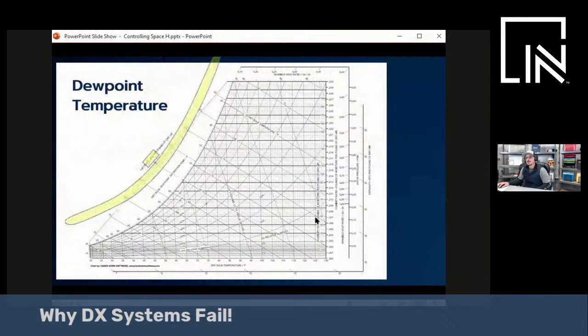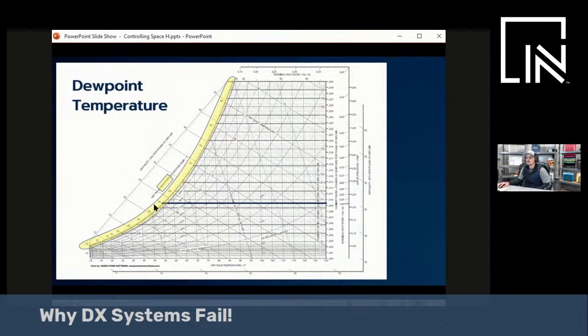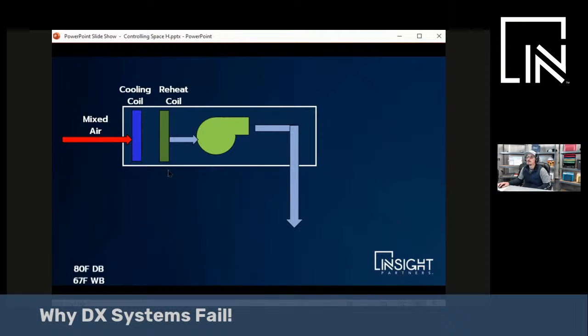If we go to our psychrometric chart, and I also have a couple videos on psychrometrics, welcome to check those out. We draw a 55 degree dew point line. Let's say this represents our space. Anything in this area above that dew point will put the air conditioning system into what we call dehumidification mode.